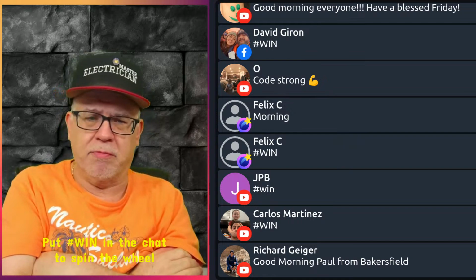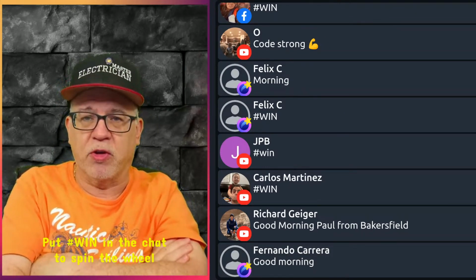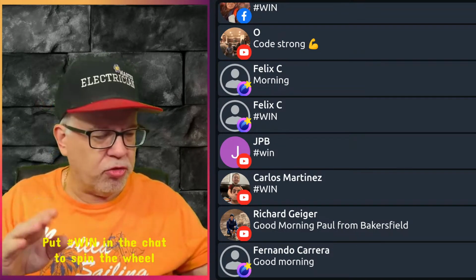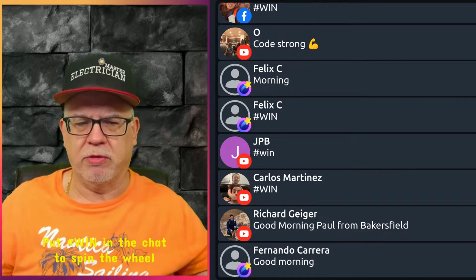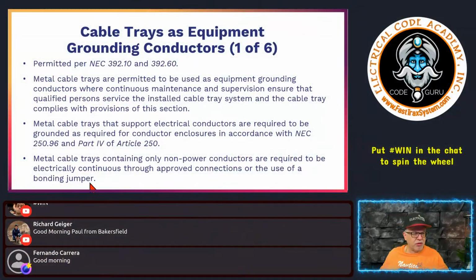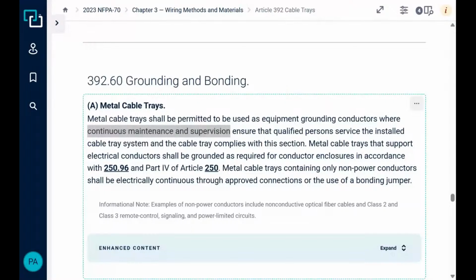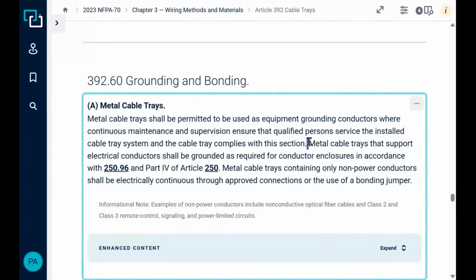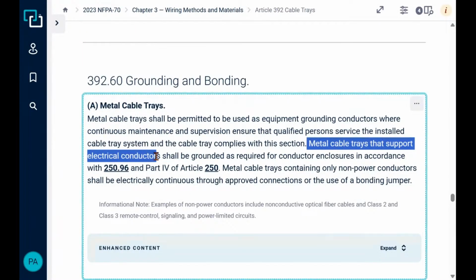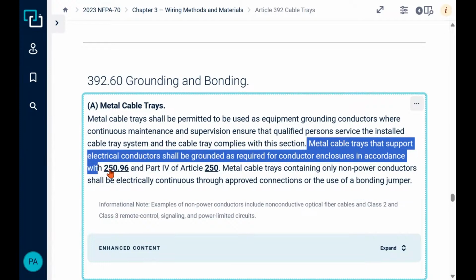No sizing involved. There's not a sizing issue about the metal got to be this. No, it just has to be evaluated and marked as for use as an equipment grounding conductor. And if that's the case, have at it. But you got to meet all those criteria, so it makes it pretty difficult for people to do that. It really does, for the most part. Well, let's go back to the code real quick. All right, so here, it says metal trays that support electrical conductors, okay, shall be grounded as required for conductor enclosures in accordance with 250.96 and Part 4 of Article 250.